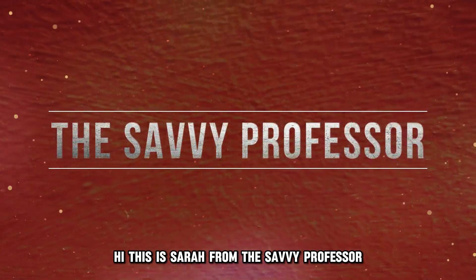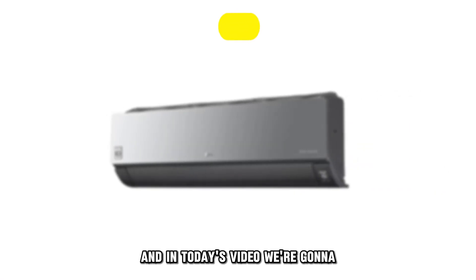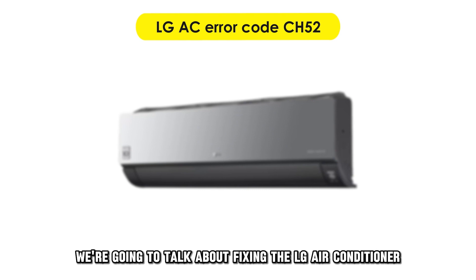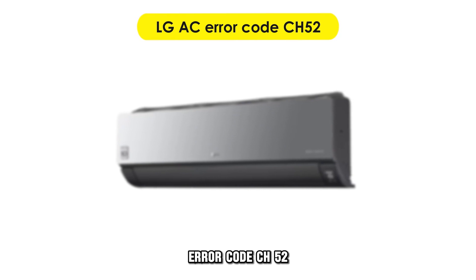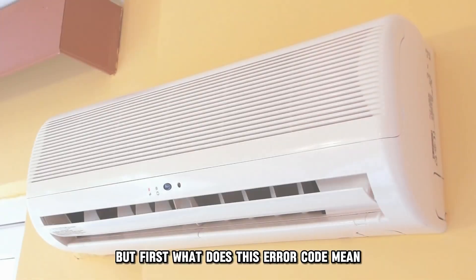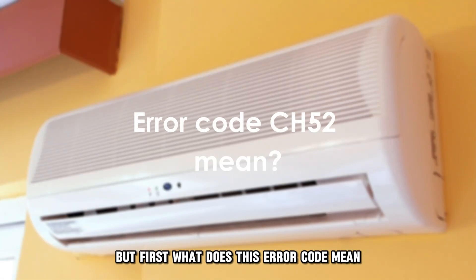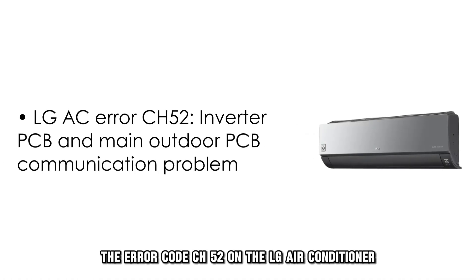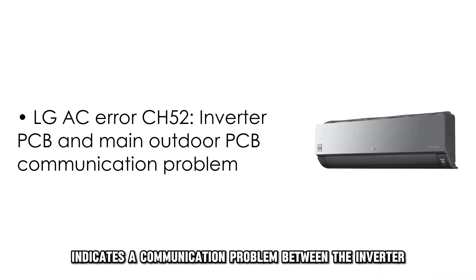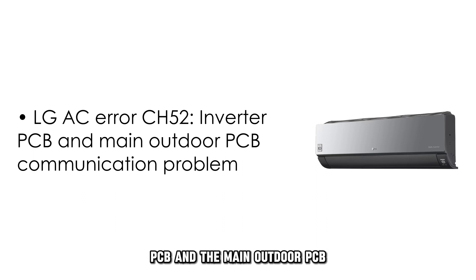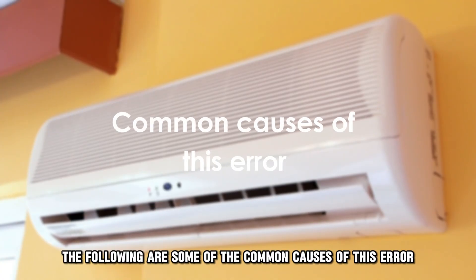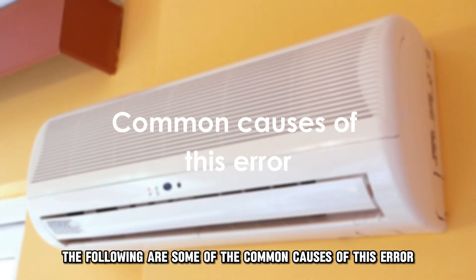Hi, this is Sarah from The Savvy Professor, and in today's video, we're going to talk about fixing the LG air conditioner error code CH52. But first, what does this error code mean? The error code CH52 on the LG air conditioner indicates a communication problem between the inverter PCB and the main outdoor PCB. The following are some of the common causes of this error.